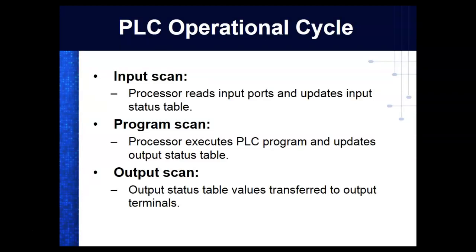Input scan, processor reads input ports and updates the input status table. Program scan, processor executes PLC program and updates the output status table. Output status table values transferred to the output, and then the thing just loops. So this thing just loops forever and ever until you take it out of the program, unless you take it out of the run mode.